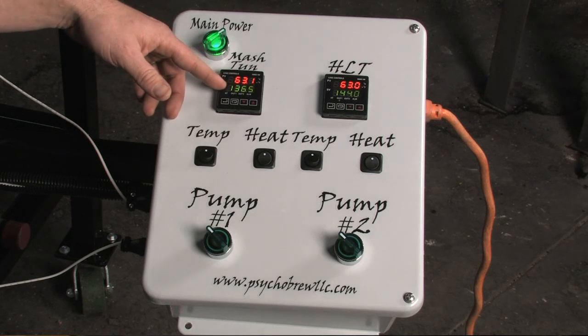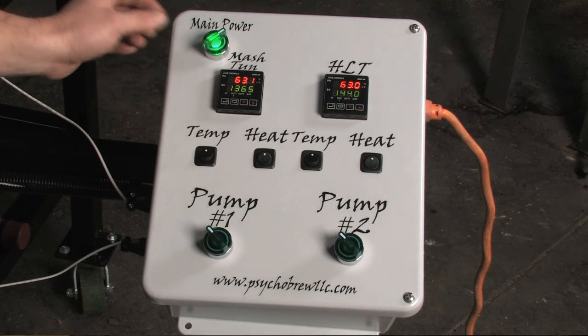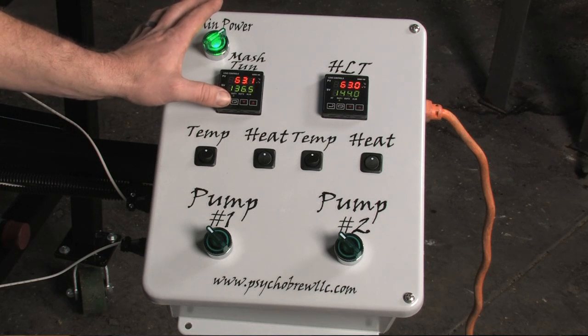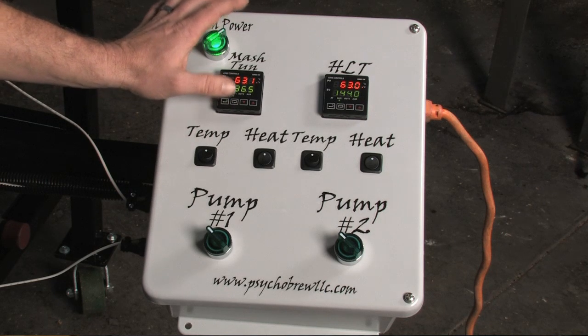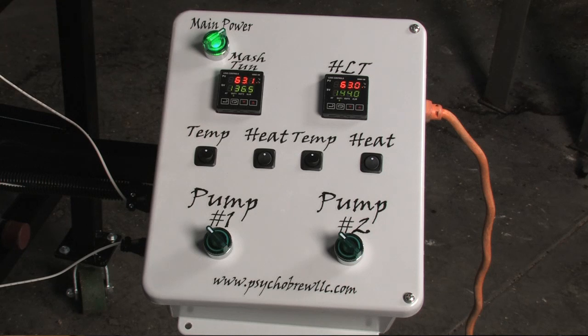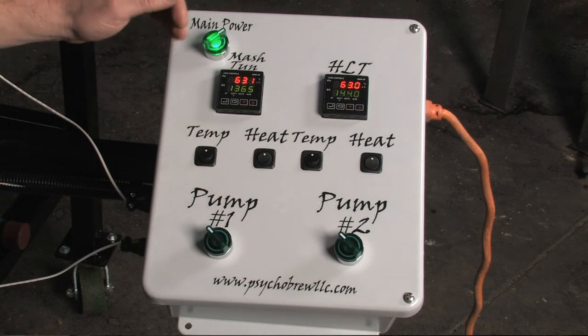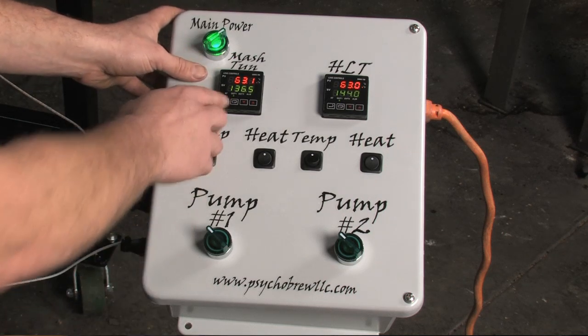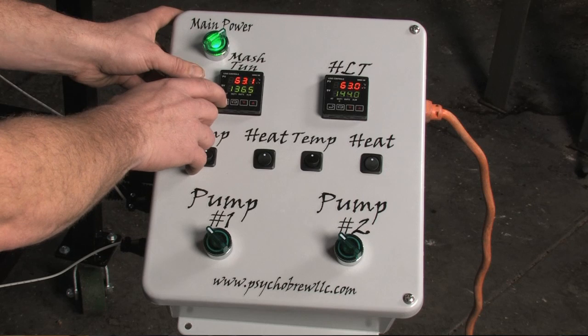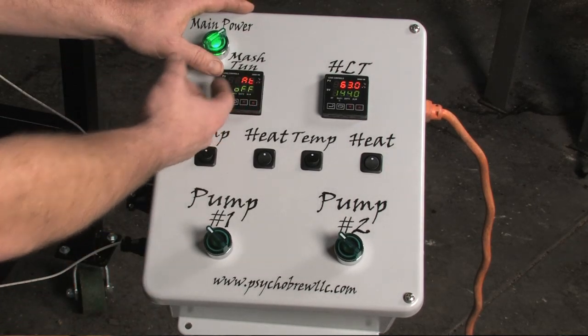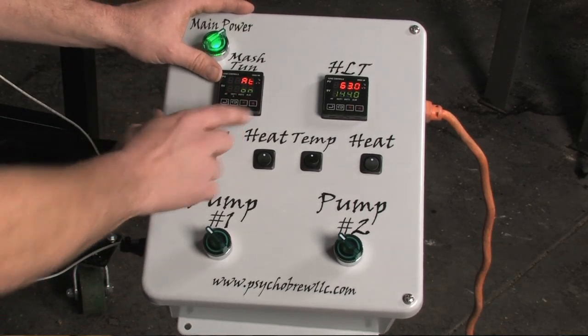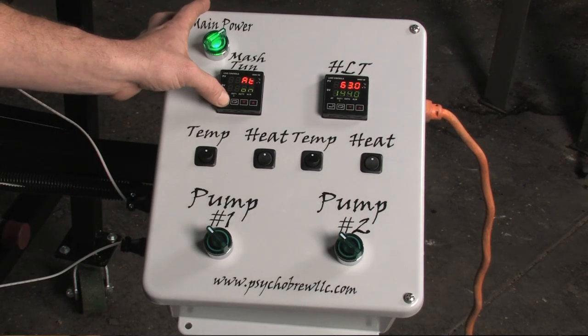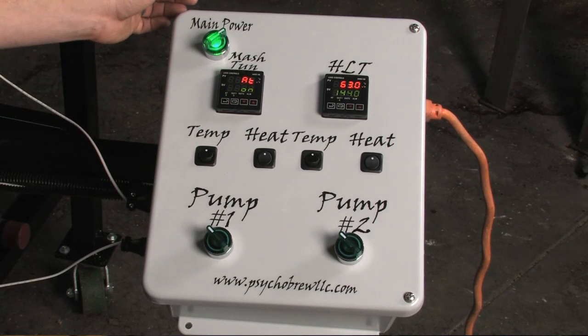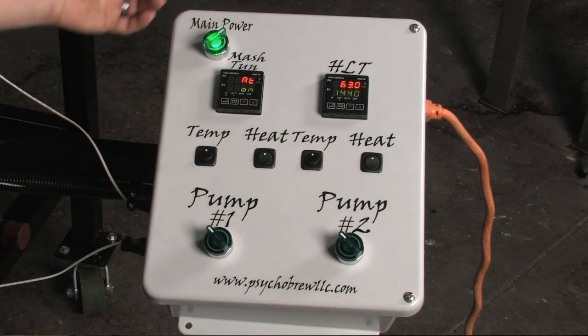One important feature of the controller is the auto tune button. When you turn this on, the controller will actually turn the burner on and off by itself, and it will learn the characteristics of how long it takes to get that temperature and shut it off automatically to try and prevent overshooting. So in order to do that, the AT button, hit that, you've got an off display. You want to turn that to a flashing green, on. Hit the enter button again. Your auto tune is on. From this point, the controller will take over. All you have to do is sit back and watch.